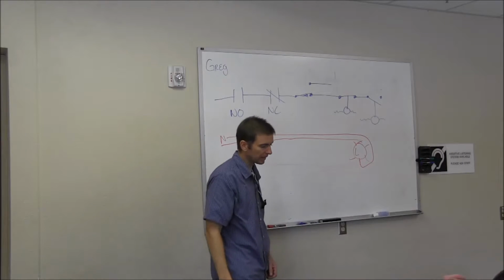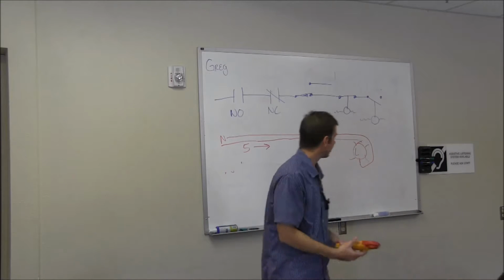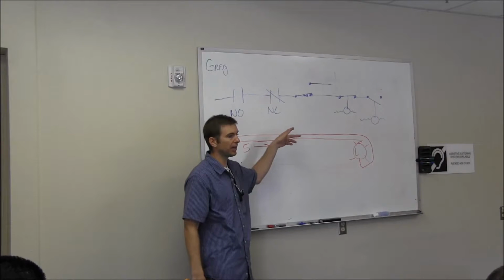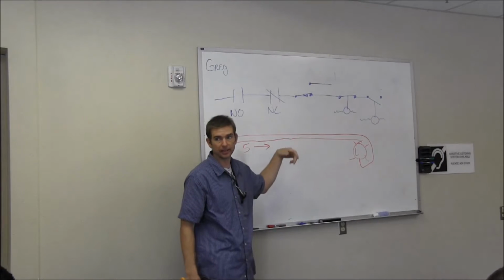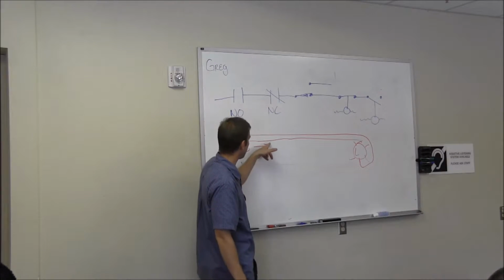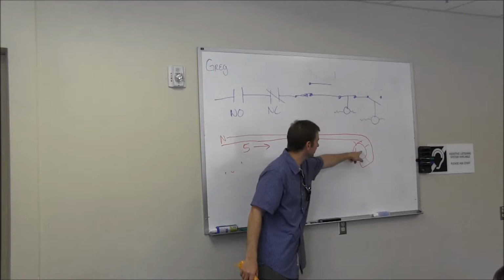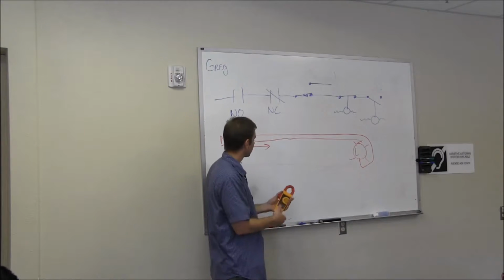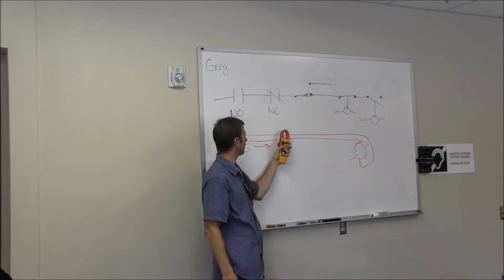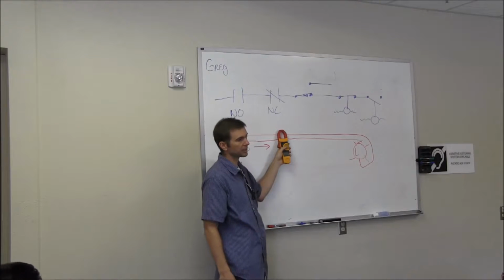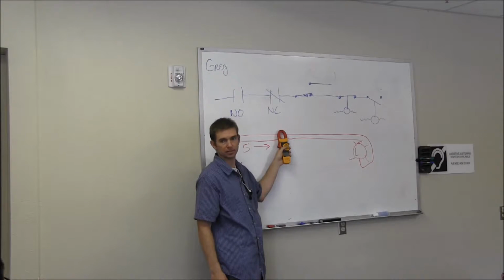Sometimes you're going to open up a box and find the wires are really close together - I don't have much slack. Maybe they're zip tied together in a panel. I want to check my amps on this conductor going out to this load. I take my amp probe and put it on both of these wires.